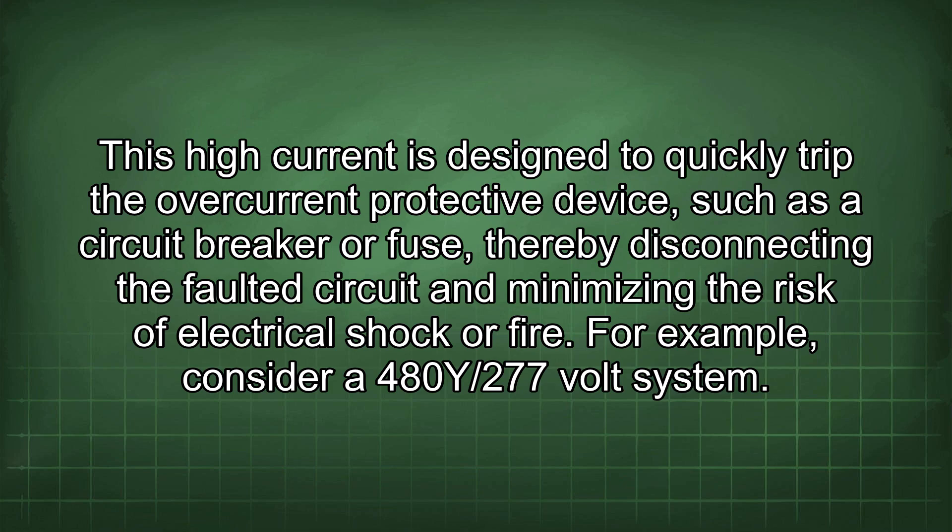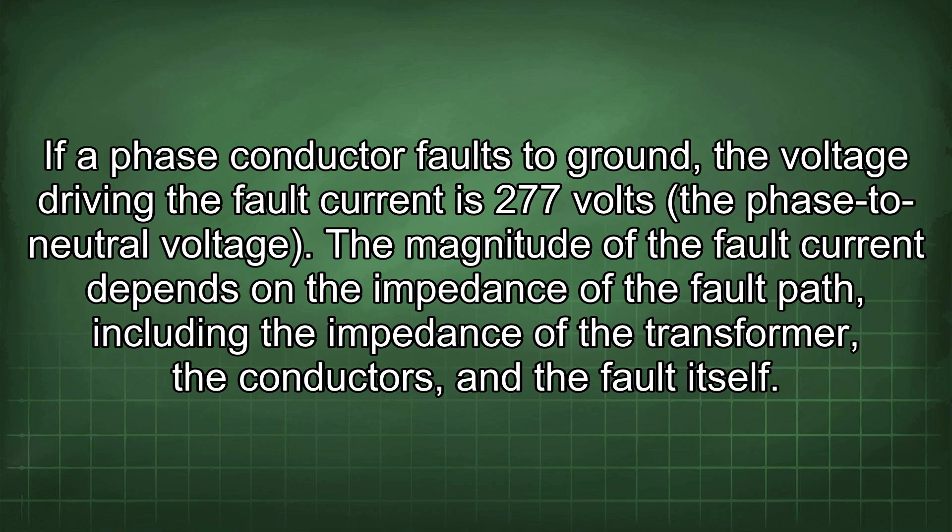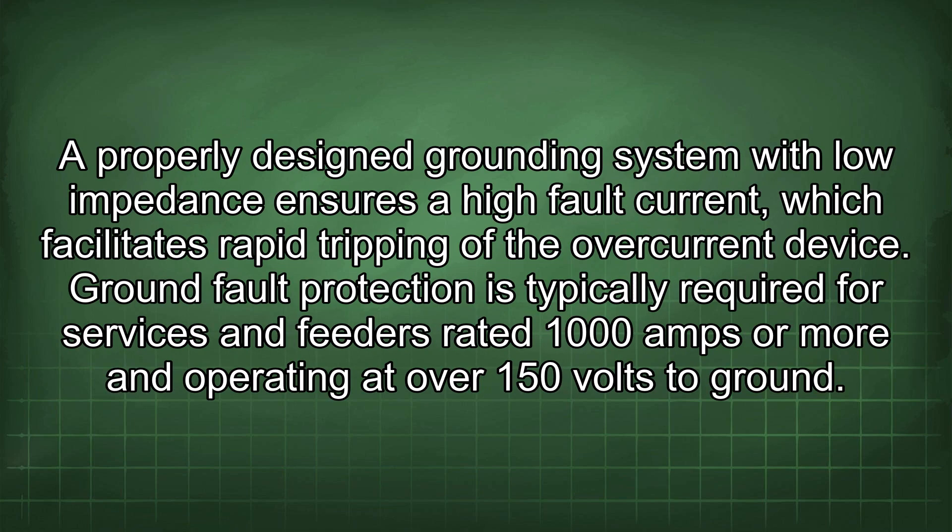For example, consider a 480Y/277 volt system. If a phase conductor faults to ground, the voltage driving the fault current is 277 volts, the phase-to-neutral voltage. The magnitude of the fault current depends on the impedance of the fault path, including the impedance of the transformer, the conductors, and the fault itself. A properly designed grounding system with low impedance ensures a high fault current, which facilitates rapid tripping of the overcurrent device.